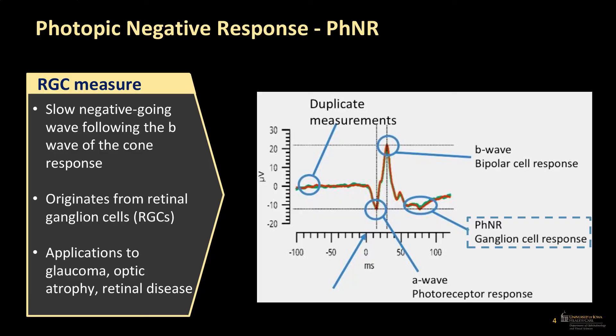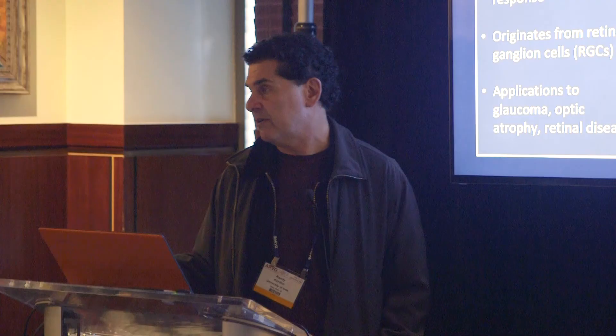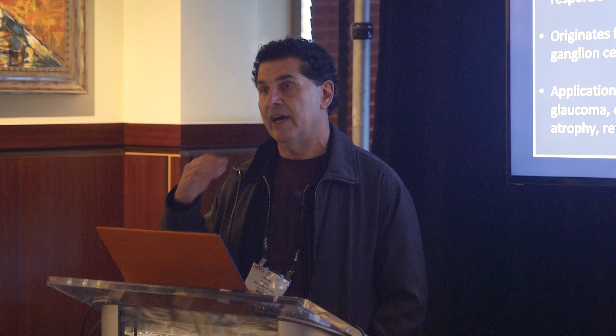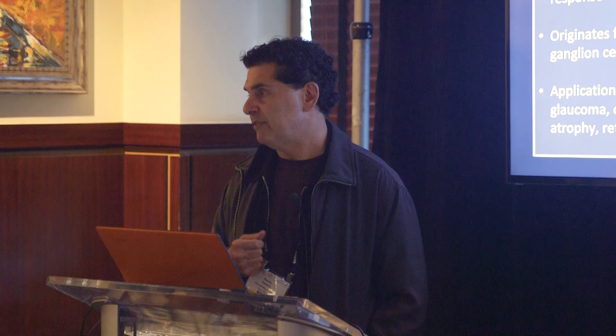Most of you are probably acquainted with the photopic negative response. Most of the literature uses a flash photopic negative, but what the RETeval is designed for is a steady-state 3.4 Hz average signal with a red stimulus on a blue background. This is a typical average response using skin electrodes, not a corneal electrode. We usually do two one-minute runs — the red and green traces are just the two runs superimposed. It's fairly reproducible because at 3.4 Hz for a minute, you have about 180 stimuli being averaged, so you gain a lot of signal-to-noise ratio from all that averaging.